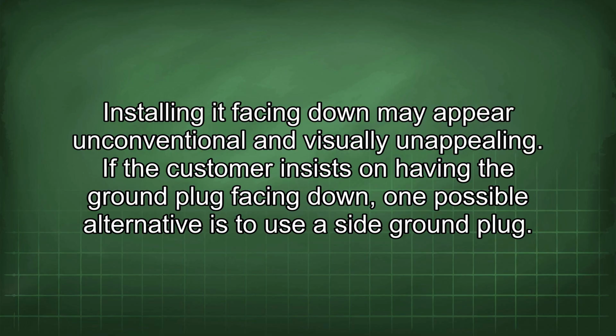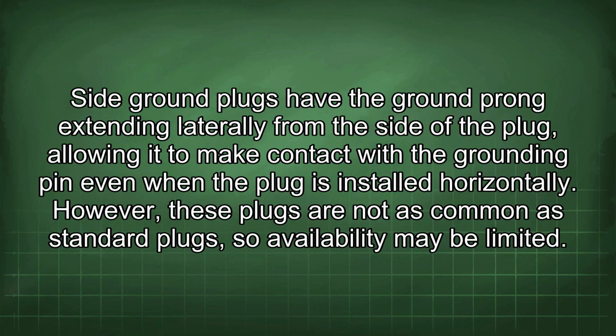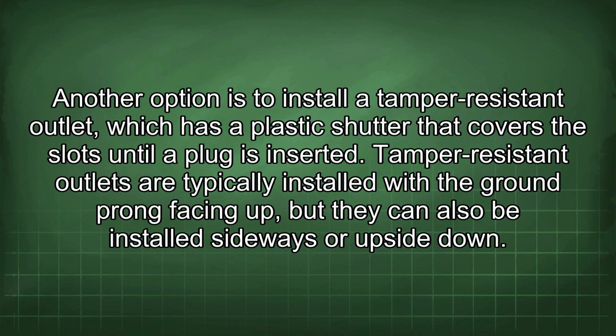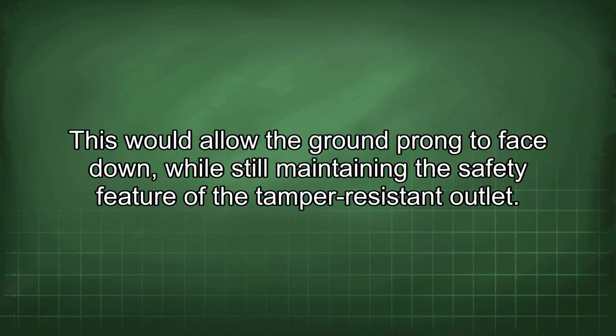If the customer insists on having the ground plug facing down, one possible alternative is to use a side ground plug. Side ground plugs have the ground prong extending laterally from the side of the plug, allowing it to make contact with the grounding pin even when the plug is installed horizontally. However, these plugs are not as common as standard plugs, so availability may be limited. Another option is to install a tamper-resistant outlet, which has a plastic shutter that covers the slots until a plug is inserted. Tamper-resistant outlets are typically installed with the ground prong facing up, but they can also be installed sideways or upside down.